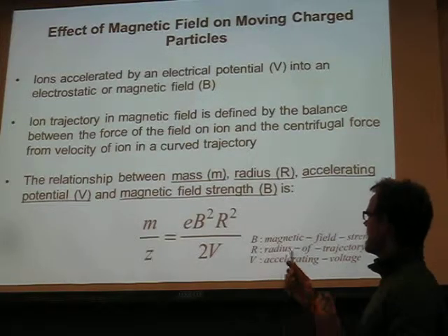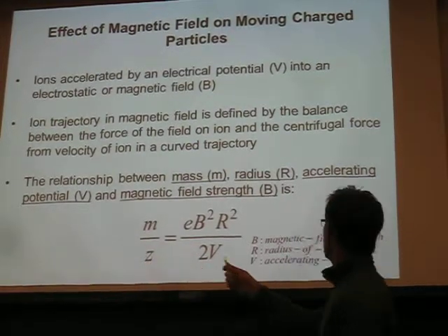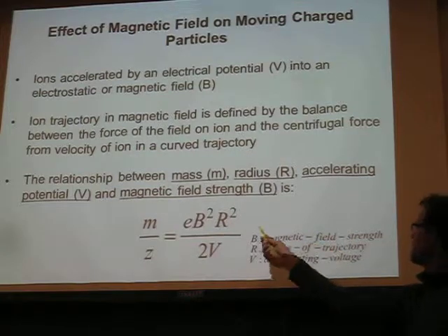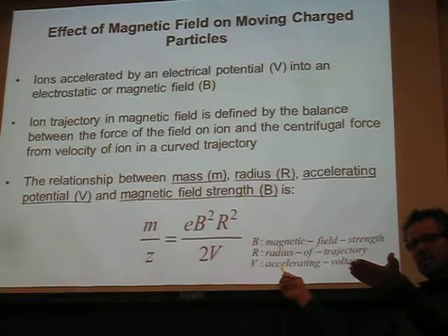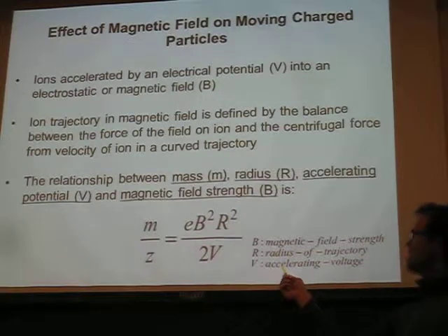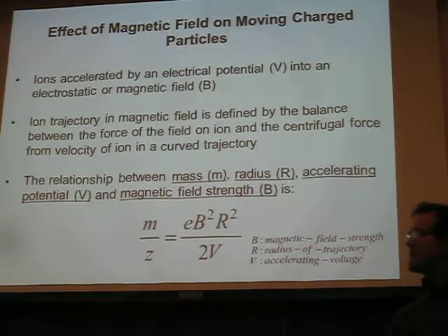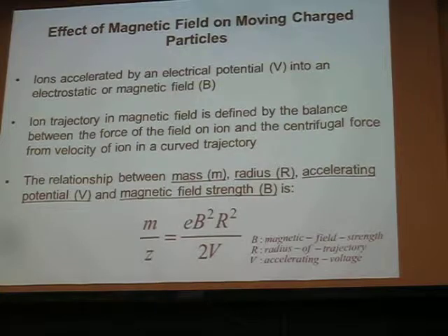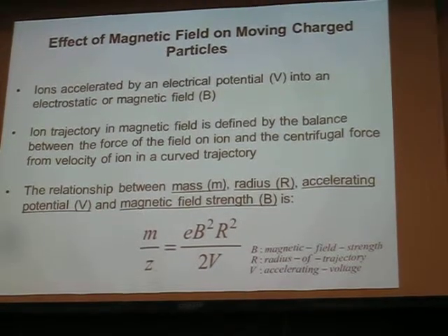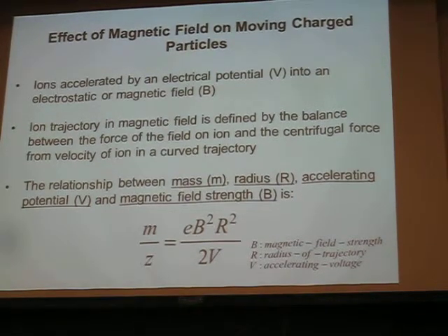They can calculate, for a given mass to charge ratio, based on the magnetic field strength, the radius of the trajectory, and how fast the ion is traveling, exactly what the trajectory is. And they do that in the programs for these mass spectrometers. You go in and say, I want to select for uranium-238, uranium-235, whatever, right? And the instrument then does the calculations for you.